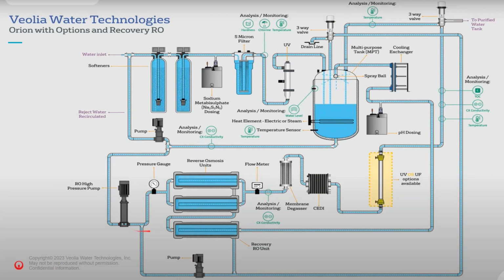The water flows through the whole of the system, through all the RO units, including the recovery RO, and all the pipework, including all the concentrate pipework, all the way up to this valve here, and this returns back to the tank here, and the concentrate through this three-way valve returns back into the tank as well. So we raise the temperature above 80 degrees. Those three temperature sensors I talk about will look to hit 80 degrees, and once they hit 80 degrees, we start the clock for 1 hour, and then we shut the system down after 1 hour. Now, if any of those three temperature sensors drop below 80 degrees during that heat up stage, we consider that a failed sanitization. So that's how we map and prove that the system has hot water sanitized.